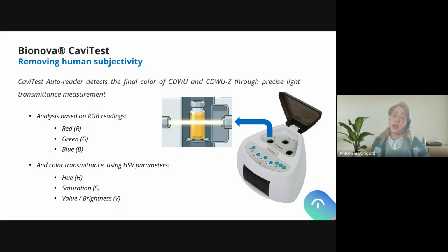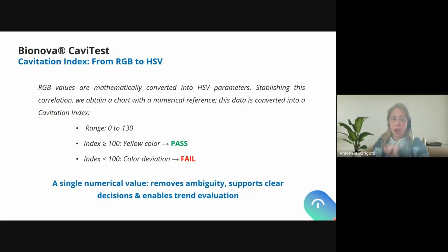HSV is hue, saturation, value, or brightness. Okay? So the RGB precise color interpreted by the machine is converted to HSV, and through a correlation we have a number that we call cavitation index. It is converted through an algorithm, RGB to HSV, and we will have a precise number called cavitation index that translates the color of the indicator to a precise number, to decide if the cavitation energy is enough or not to guarantee the removal of organic residues from my instruments.